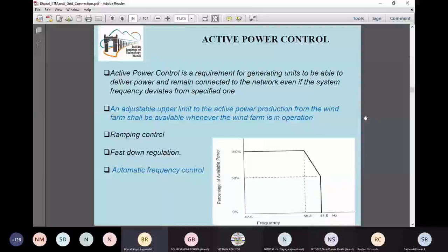For example, if 100 units of energy are available in the moving wind coming out of a wind turbine system, then why not set a limit of 95 units? That gives us 5 units of possibility to increase the power output from the wind energy control system. But a major drawback of this system is that we are continuously losing 5 units of energy because we are not operating at the maximum power point.